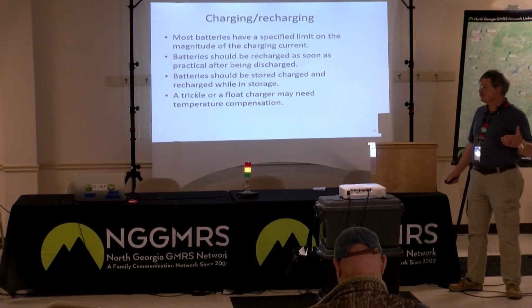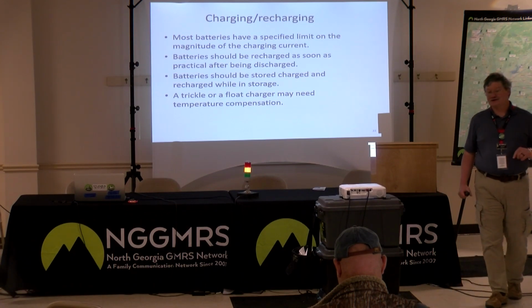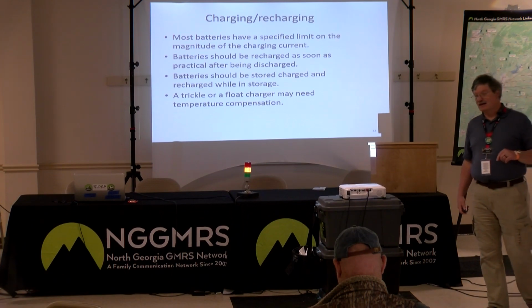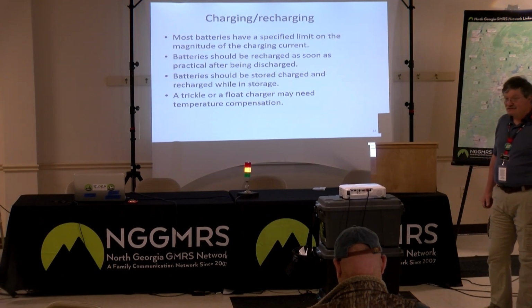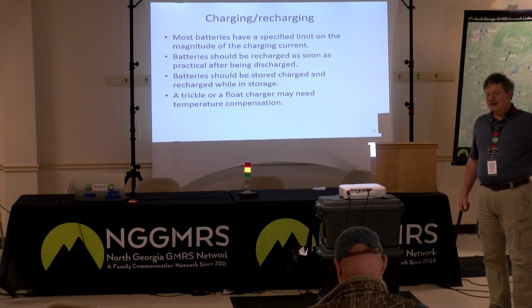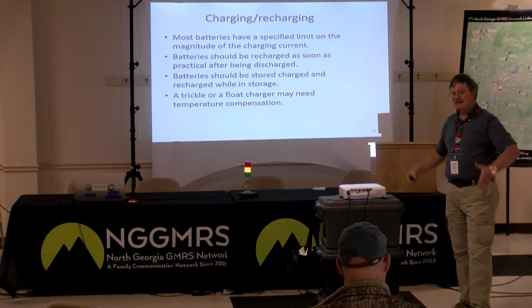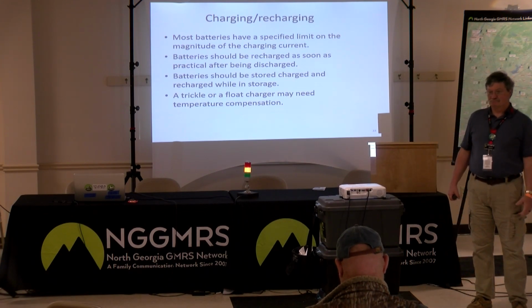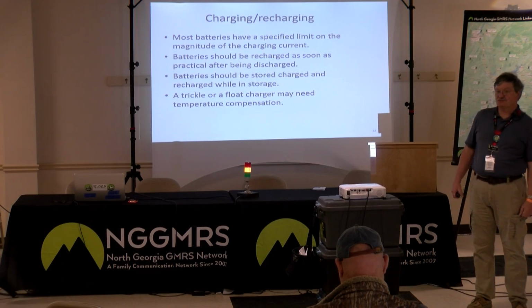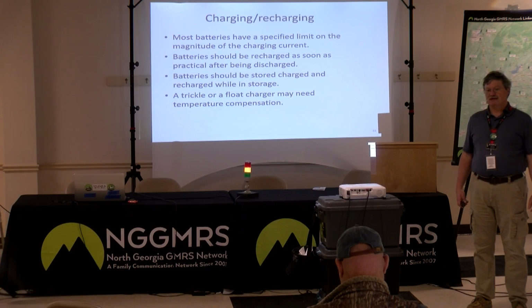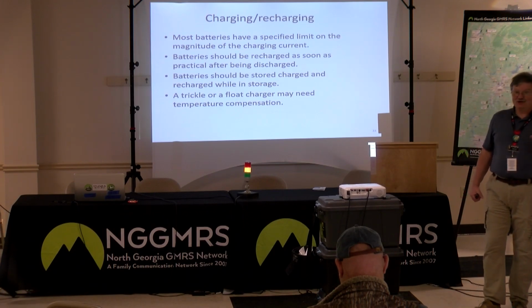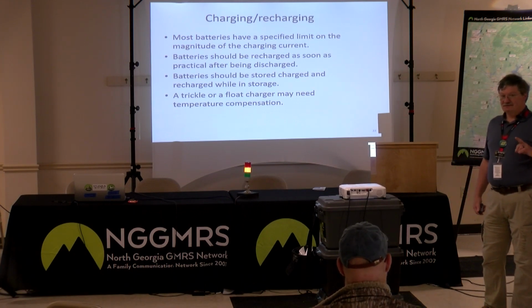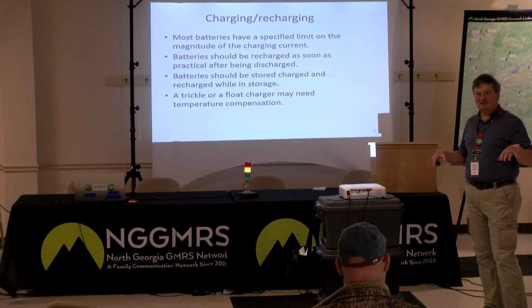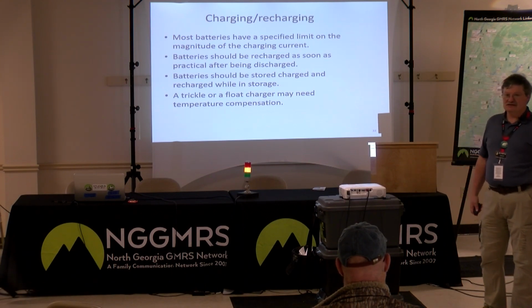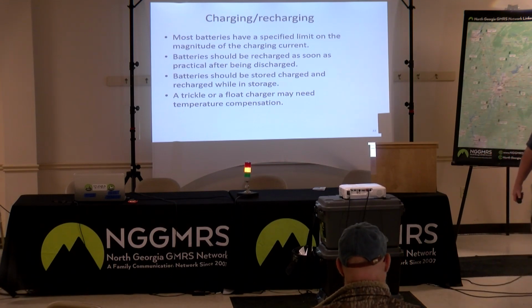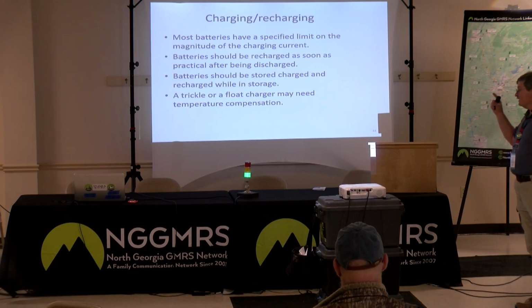Lead-acid batteries tend to degrade if they're not kept fully charged. If you've got a lead-acid battery, the manufacturer - again, I was working for a battery manufacturer - if we made a battery, we put it on the shelf day one, and if that battery was still on the shelf at six months, we had to put it back on charge. Every six months, and this is a new battery in a good, clean storage environment. If the battery's dirty, you get more self-discharge on it and all, so over the top of it, you need to keep them charged. I would say a nice thing would be once a month, this way it's ready to go at any time.